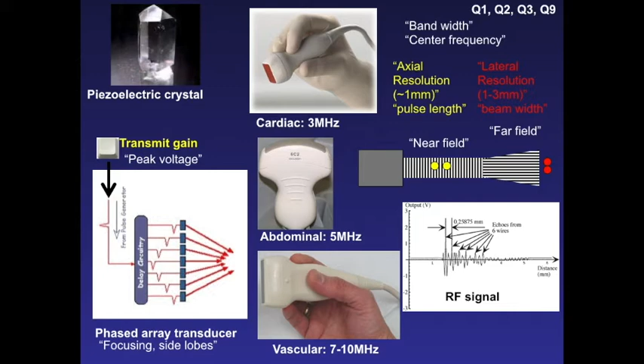So the RF signal comes back, and then we can bump up what's called the receiver gain. So this is not hitting the bell. This is not the transmission gain. This is the receiver gain. This does not add any more power to the tissue. This is just listening better. So the receiver gain, we use TGCs, time gain compensation. Now, on your devices, they have already been programmed, but on a full machine, you can boost up the signal in the far field to account for attenuation so that the image looks consistent throughout its depth.